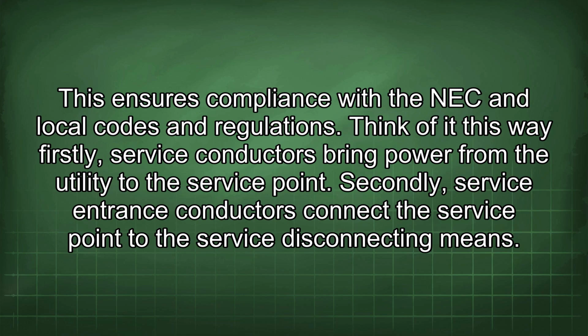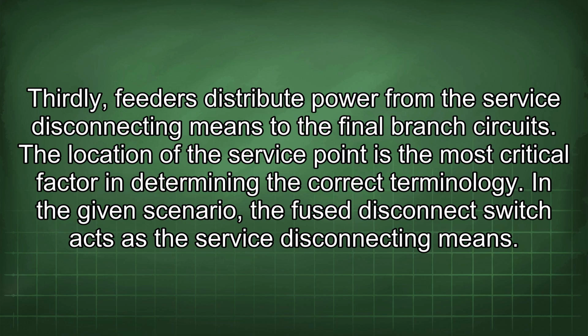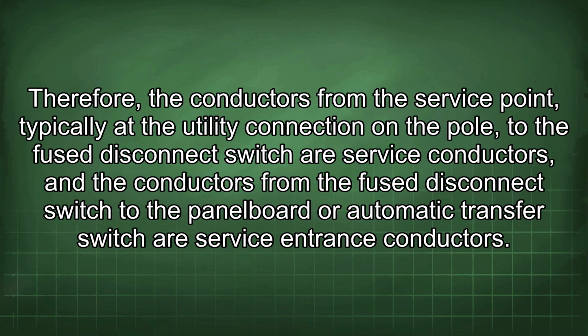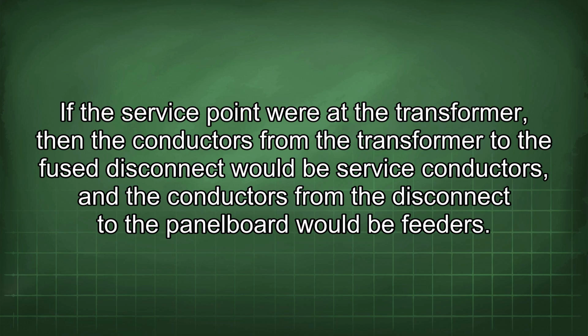Think of it this way: firstly, service conductors bring power from the utility to the service point. Secondly, service entrance conductors connect the service point to the service disconnecting means. Thirdly, feeders distribute power from the service disconnecting means to the final branch circuits. The location of the service point is the most critical factor in determining the correct terminology. In the given scenario, the fuse disconnect switch acts as the service disconnecting means. Therefore, the conductors from the service point, typically the utility connection on a pole, to the fuse disconnect switch are service conductors, and the conductors from the fuse disconnect switch to the panel board or automatic transfer switch are service entrance conductors. If the service point were the transformer, then the conductors from the transformer to the fuse disconnect would be service conductors, and the conductors from the disconnect to the panel board would be feeders.